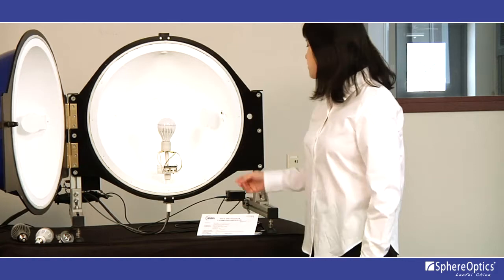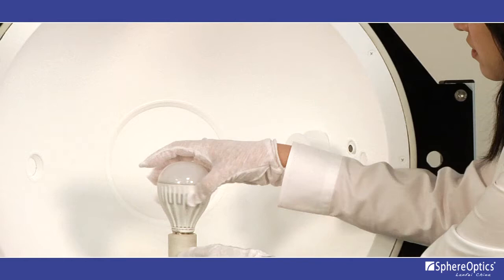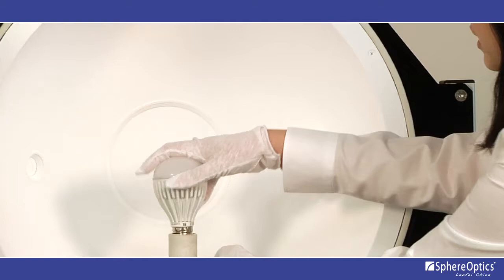Each system includes an integrating sphere in either half-meter or two-meter size, configured for both 2pi and 4pi measurement geometries. Choice of size depends on the application, with typical DUTs ranging in size from small LED chips to large street lights.